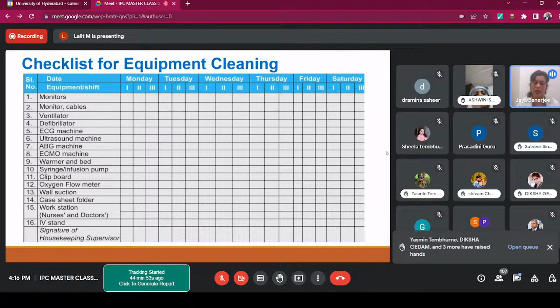Next, please. This is again the checklist for equipment cleaning we can use, and we can customize it according to our organization policy. Next. Glutaraldehyde efficacy must be checked. Once activated, glutaraldehyde can be used for 14 days, and it should be checked for each and every soak of the item. Here the glutaraldehyde chemical indicator strips show acceptable and rejectable results. You can see when we can accept and when we can reject. Next.